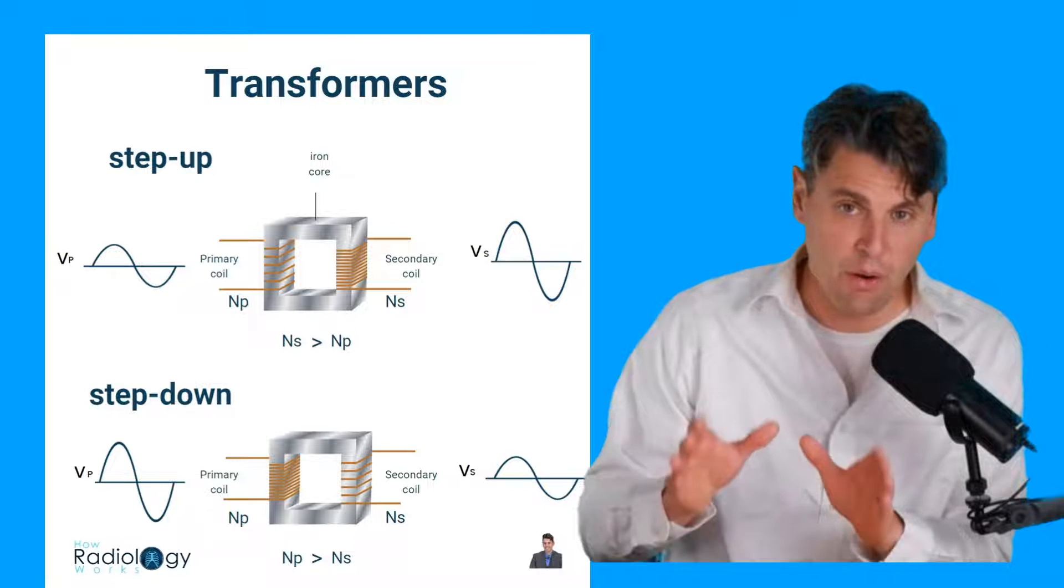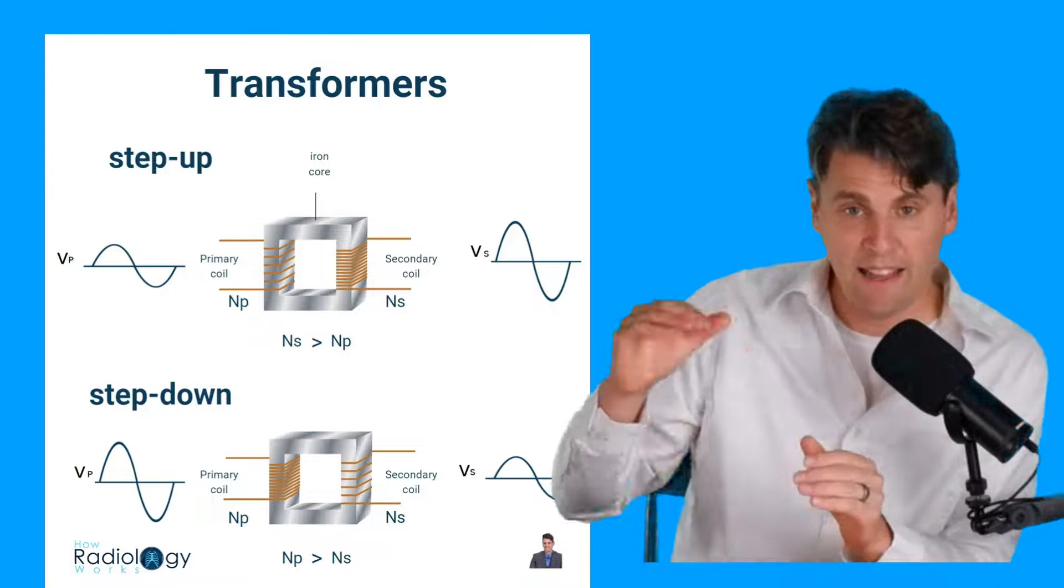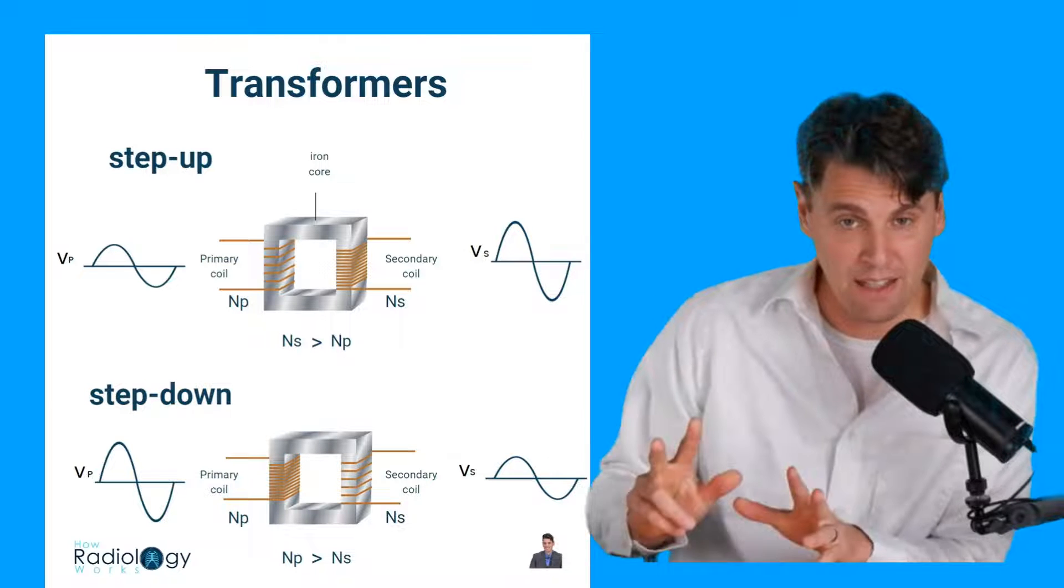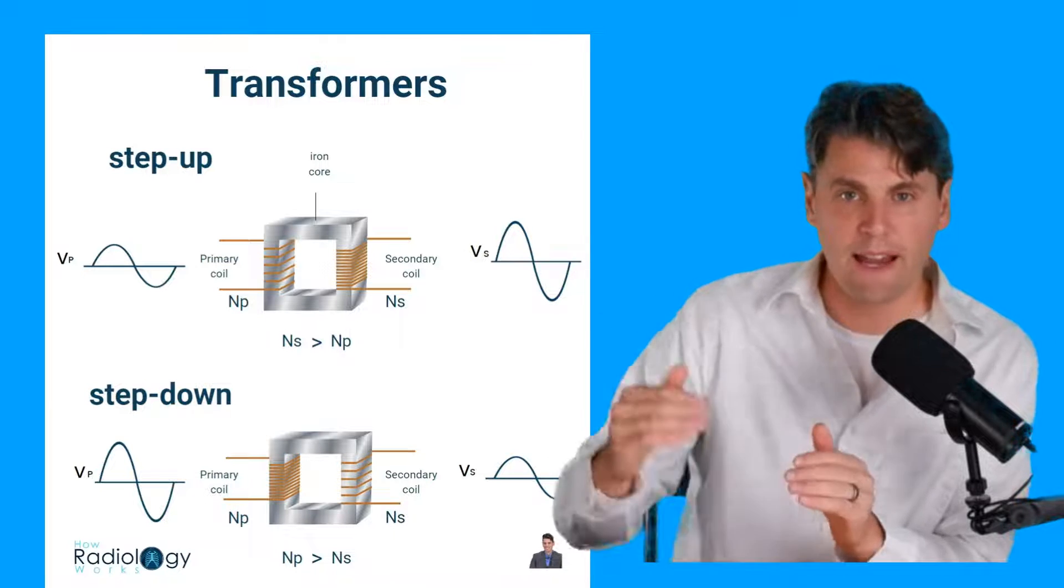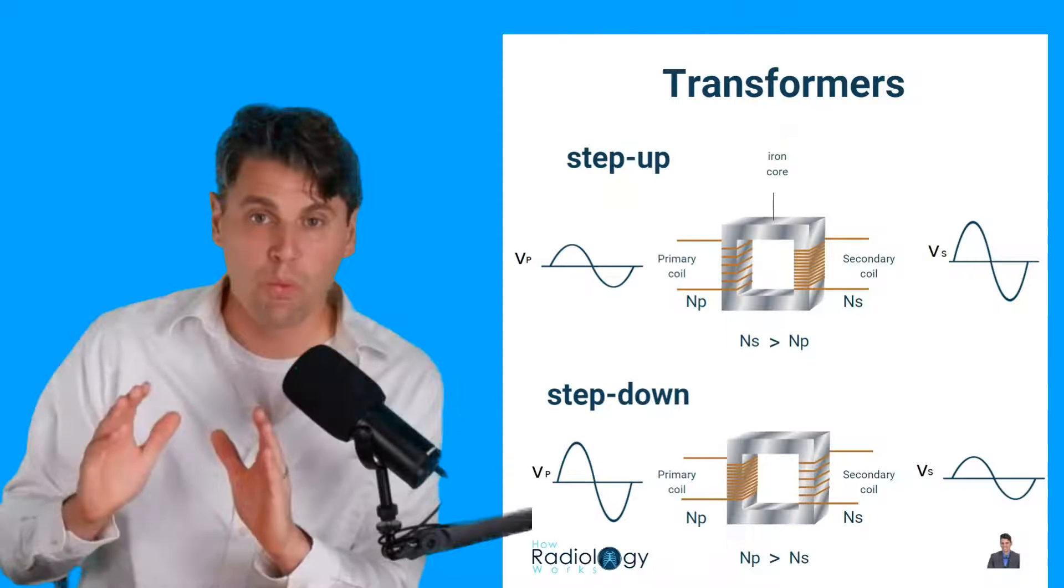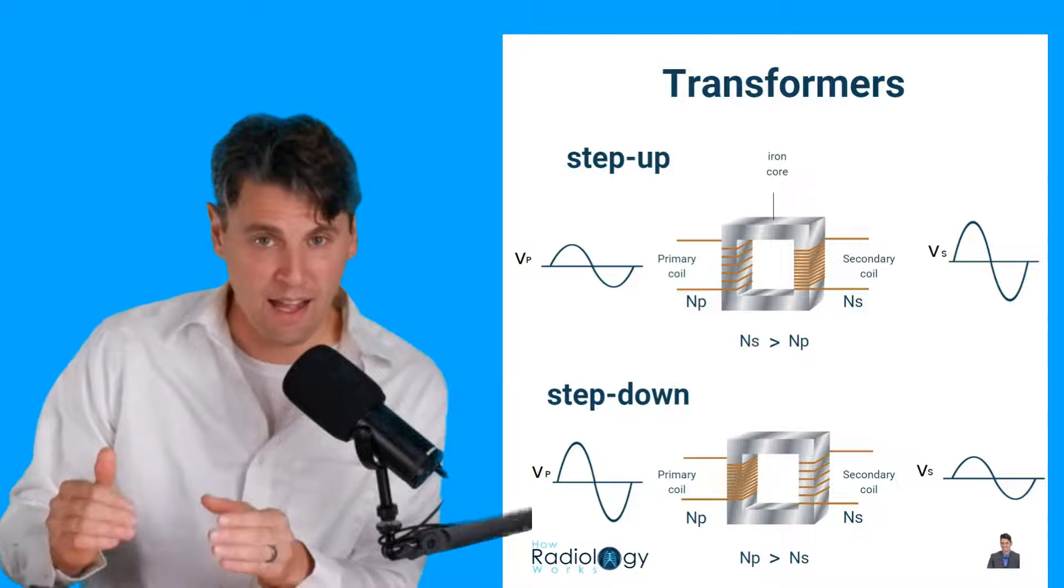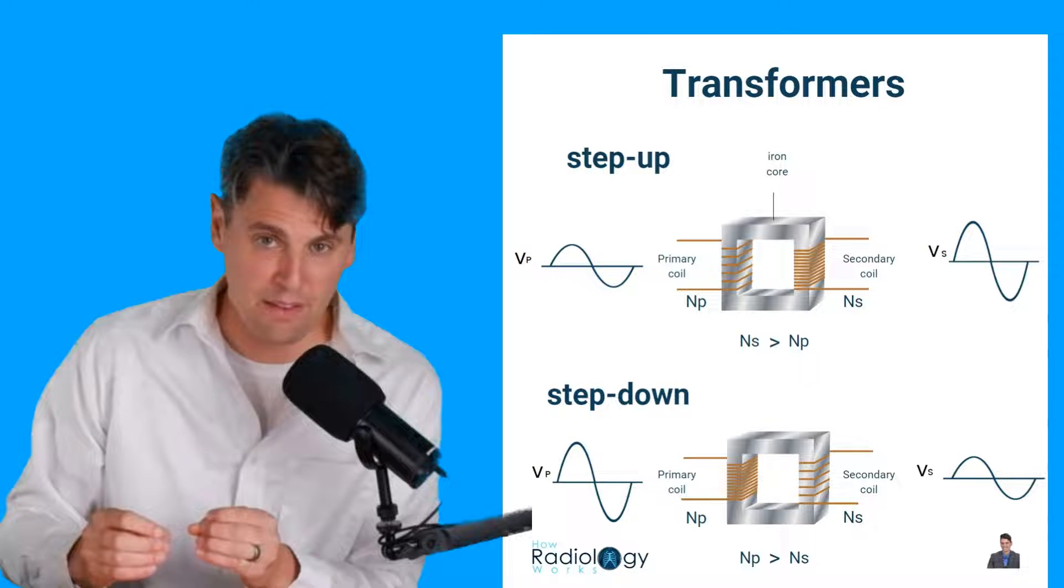In our x-ray circuit, we're going to talk about why we want to do that on the filament or heating circuit because we actually want a lower voltage there. We want a high current or high amps on that circuit. So that's where we want a step down transformer.